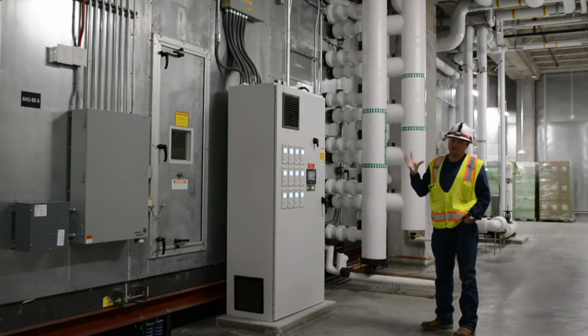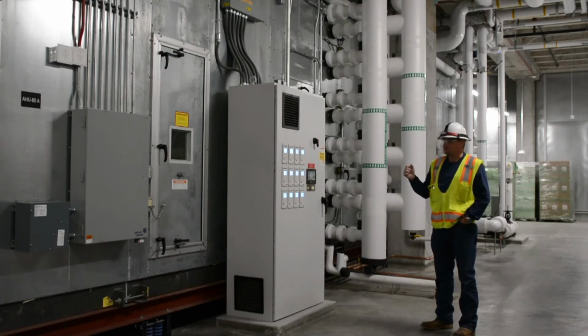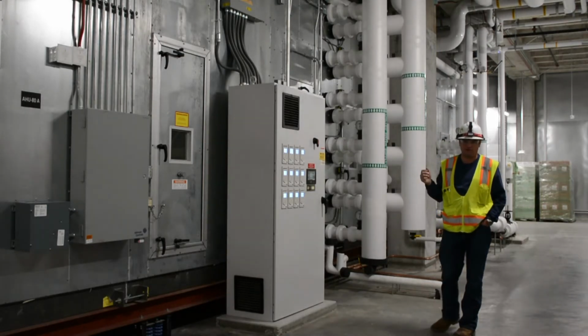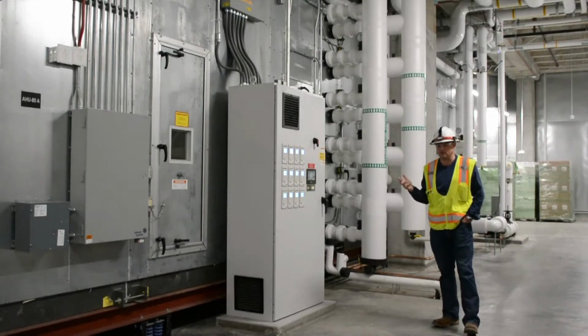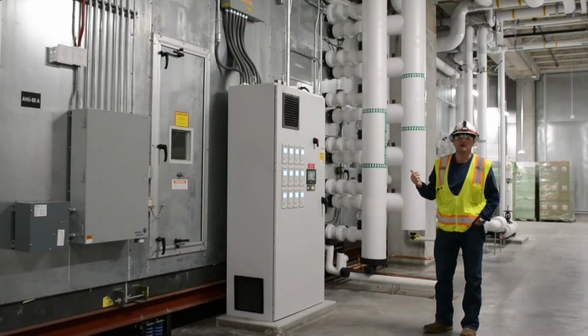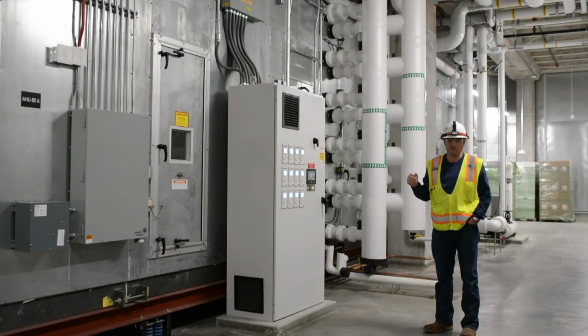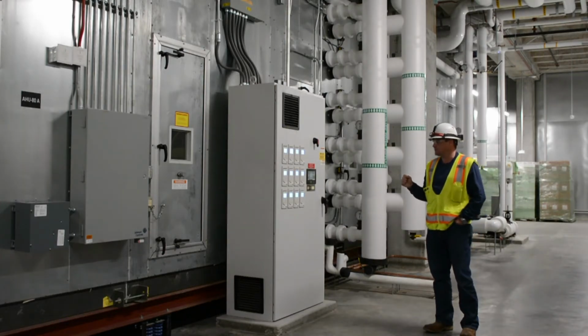If a fan goes out of balance, it's probably because it lost one of the weights for balancing that wheel from the factory. And if you do see vibration or anything of that magnitude, you need to just replace the entire blower wheel. You can't rebalance those wheels, as it's very difficult to do in the field, and it costs less money just to order a new one rather than doing a field balance of the wheel itself.